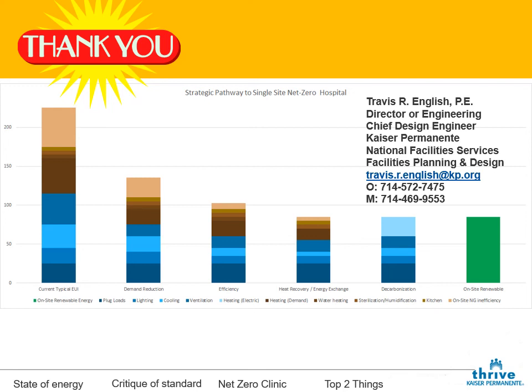There's no solar load. There's no heating load. There's no outdoor cooling load. Any light in the building that can be off is off. The patients are asleep. All their lights are off. All the medical equipment in the building is either off or it's on standby. The parking lot is 80% empty. The staffing is down to 1 staff per 1,000 square feet or 1,500 square feet. There's no load in that building. I mean, on paper, you could show that there's maybe 5 BTU per square foot or something like that.